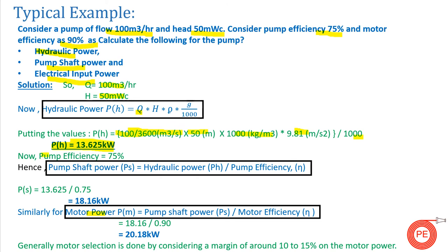With pump efficiency of 75 percent, the pump shaft power = hydraulic power / pump efficiency = 13.625 / 0.75 = 18.16 kW. For motor power, the formula is pump shaft power / motor efficiency = 18.16 / 0.9 = 20.18 kW. So the power consumption of the motor is 20.18 kW. When designing the system, the selected motor should have a capacity greater than this value.